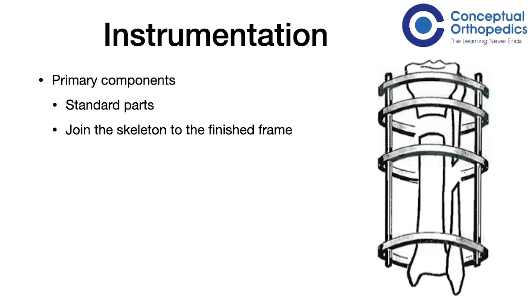The Ilizarov device is a circular external fixator. Its principal component is a ring with a flat surface and multiple holes. In a complete set of Ilizarov fixators there are different sizes of rings corresponding to the diameters of the patient's limb. When the rings are connected to the bone and to each other, the resultant frame replicates the cylindrical shape of a tubular cortical bone shell, but larger than the bone. This design allows the fixator frame to accommodate very high axial, torsion, compression, shear forces, and combined torsion-compression loading.